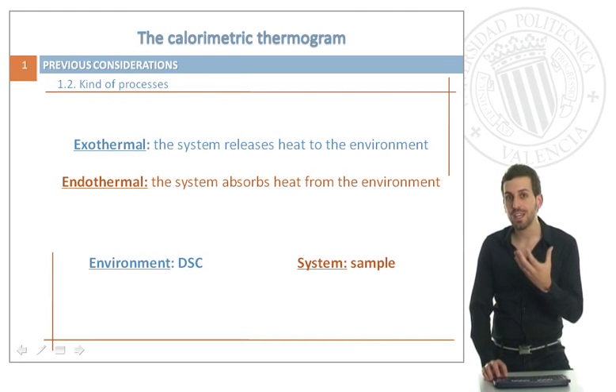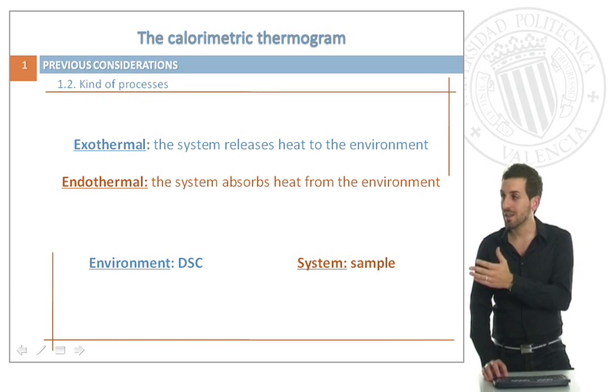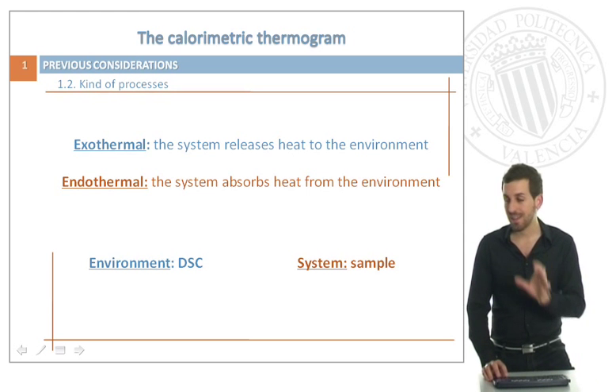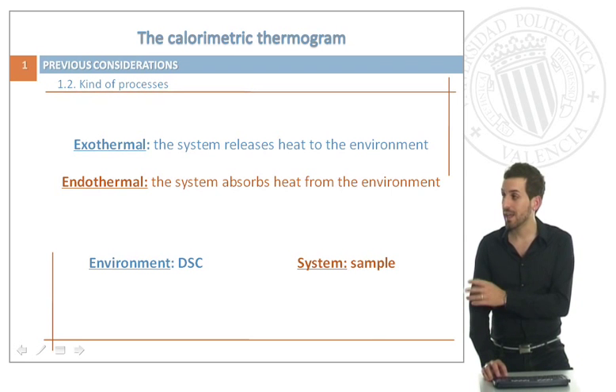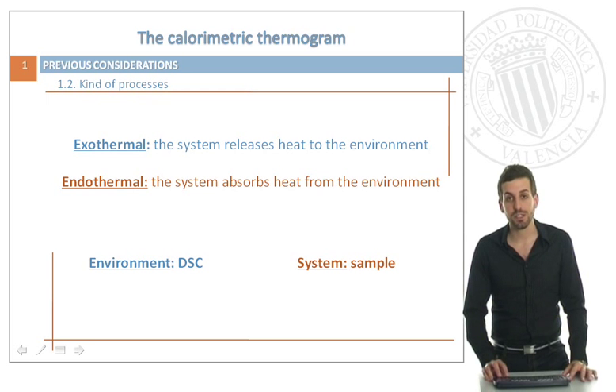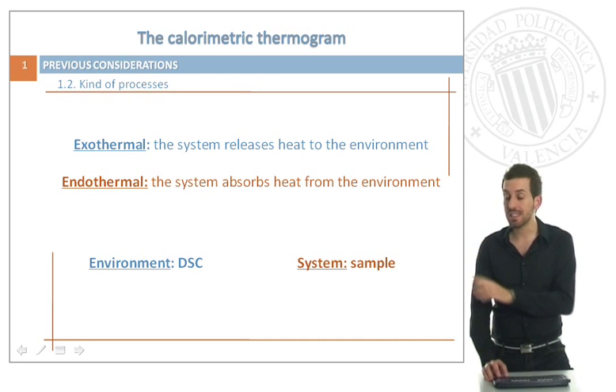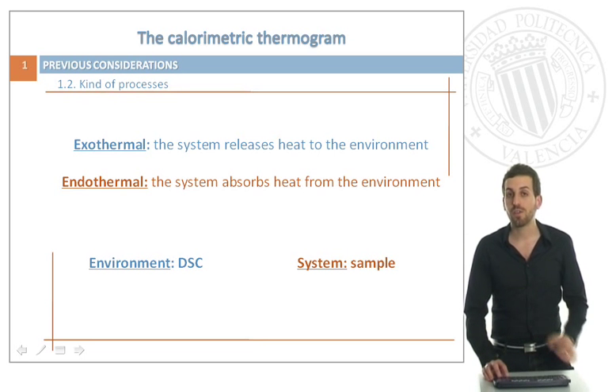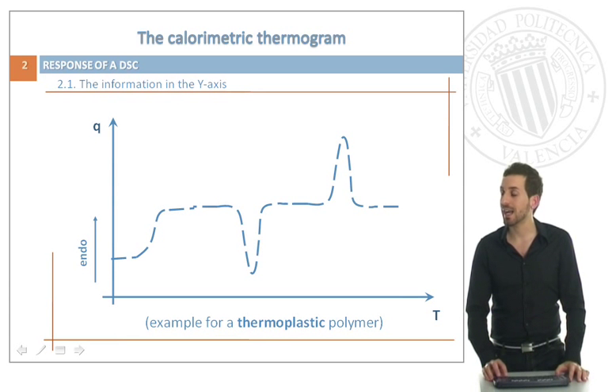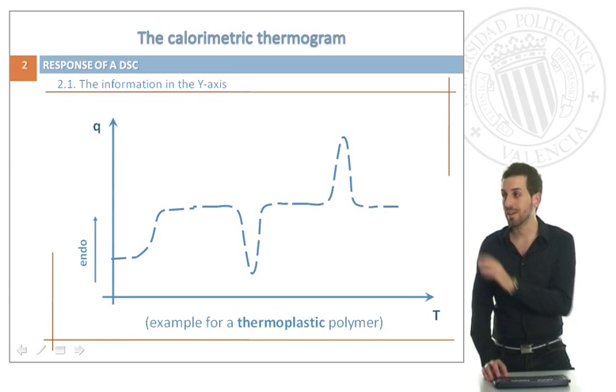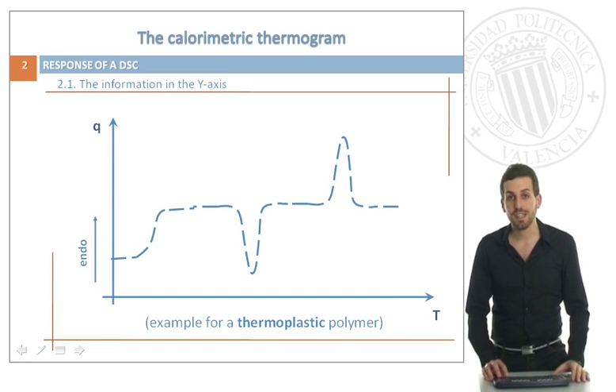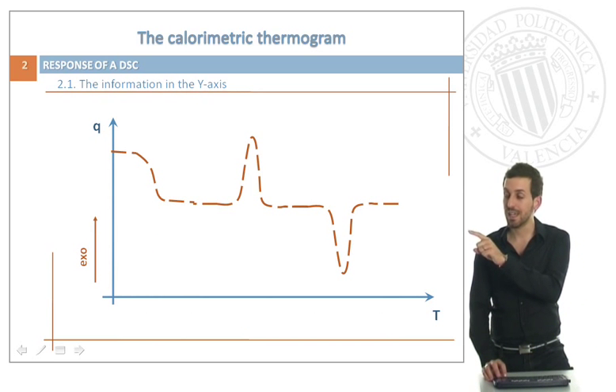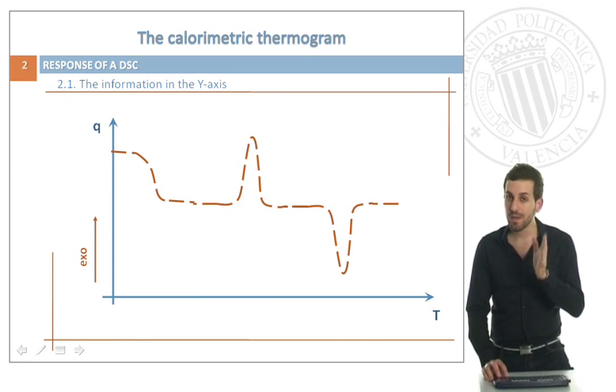What we are really going to see are changes in exothermal transitions as well as endothermal transitions. If we set that our environment is the DSC as a device and our system is the sample, we define exothermal transitions as those in which the system is releasing heat to the environment, and endothermal transitions as those in which the system is absorbing heat from the environment. It is very important to know what sign is shown on the y-axis — if it says 'endo,' the endothermal transitions go in the positive direction. On the other hand, if we see 'exo,' those transitions in the positive axis are the exothermal ones. So be very, very careful.